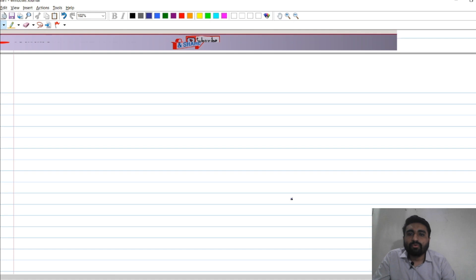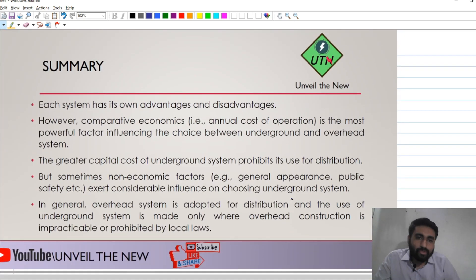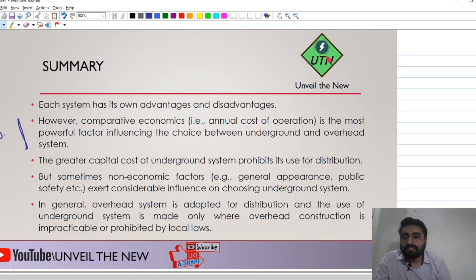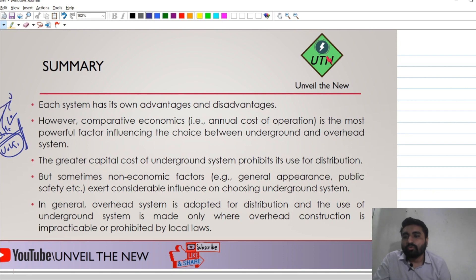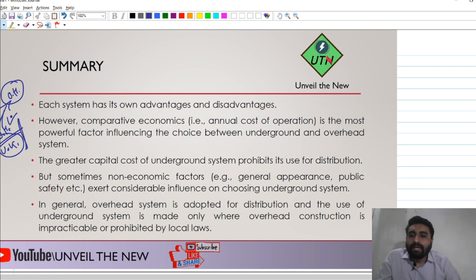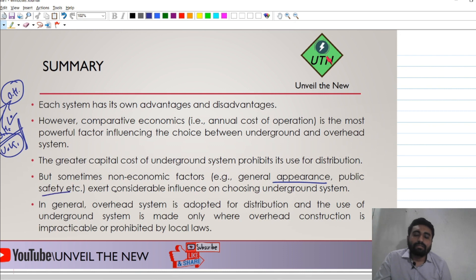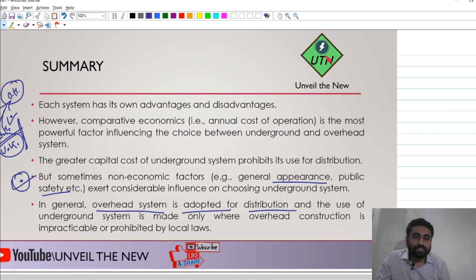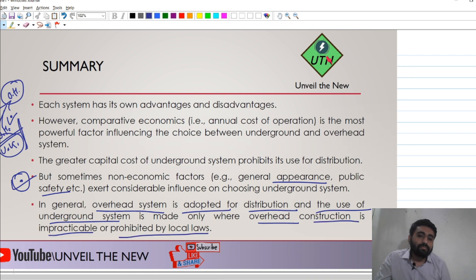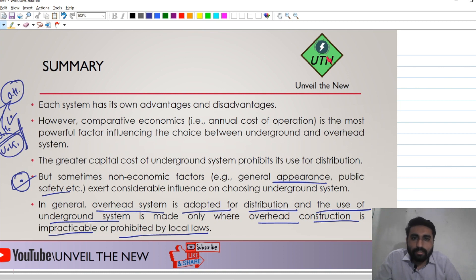In summary, each system has its own benefits and disadvantages. If we consider the economic factor, the overhead system is much more economical compared to the underground system, which motivates people to use overhead systems — which is why India mostly uses overhead systems. However, if we set aside the economic factor and consider parameters like general appearance, public safety, and maintenance cost, then the underground system is the clear winner. In general, overhead systems are adopted for distribution, and underground systems are used only where overhead construction is not possible or is prohibited by local laws.